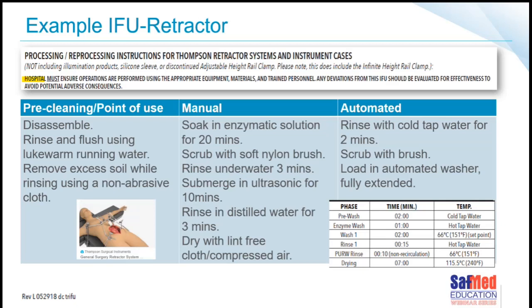No. It stipulates you want a pre-wash with cold tap water. Temperature of water matters, we'll talk about that just now, for 2 minutes. Then you want an enzymatic wash. Then you want the main wash for 2 minutes, and the temperature needs to be at 65 degrees. Then you want the rinsing, and then you want the rinsing with purified water, and then you want the drying cycle. And the drying cycle should be, I think that's 7 minutes, if I can see clearly, at 115 degrees. That's the requirements.